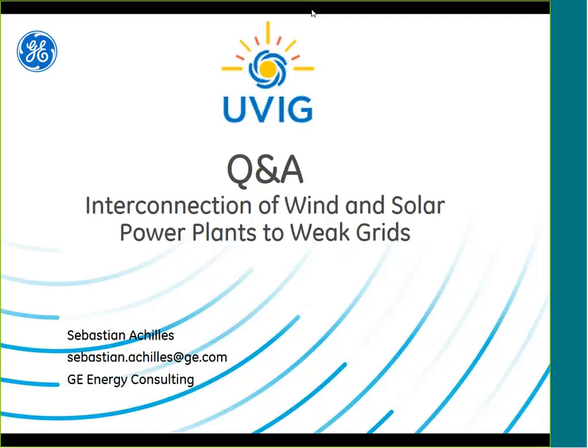Yeah, in our experience that would be ideal, but it doesn't work too well. This is a challenge, and I really appreciate the question because I should probably have elaborated on this. Some of the phenomena we looked at are really fast. If you look at the interactions, they're things of tens of milliseconds. If you look at the voltage collapse, some things are hundreds of milliseconds. So typically, sending a curtailment signal to reduce the power of a plant is too slow to avoid the problem. So what you could have is a contingency, and based on the contingency, you instruct a plant level controller to curtail. But by the time that curtailment is actually effective, the plant has already tripped or something else in the grid has already tripped.